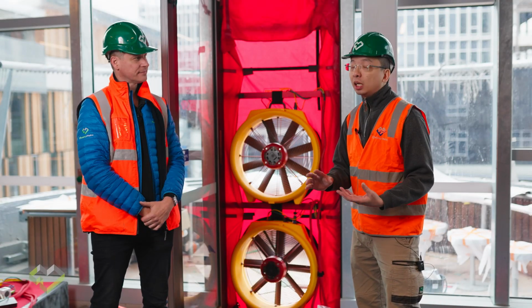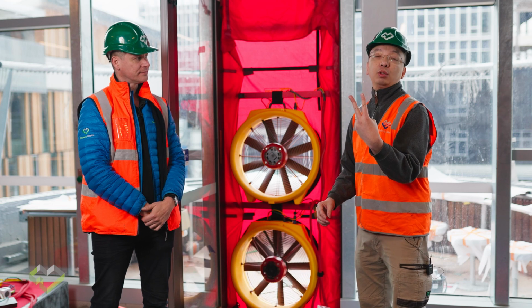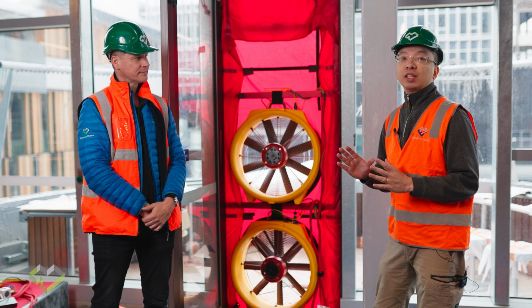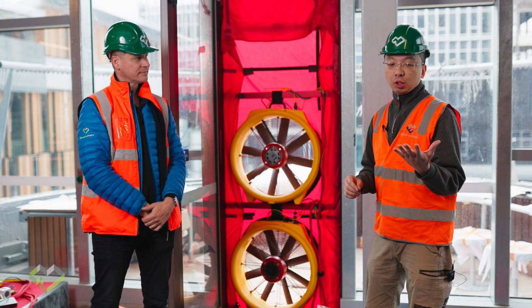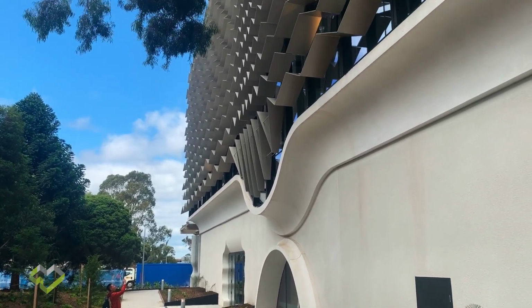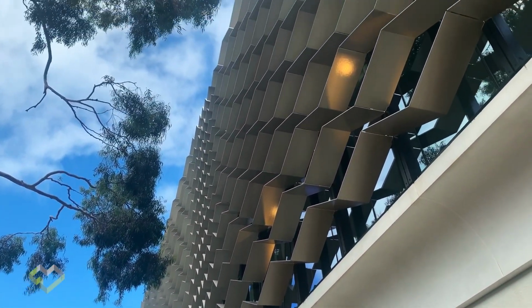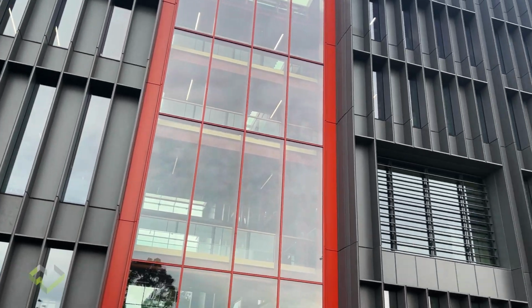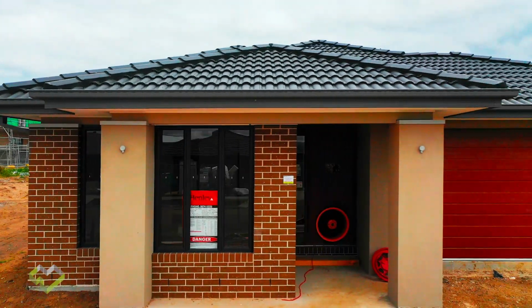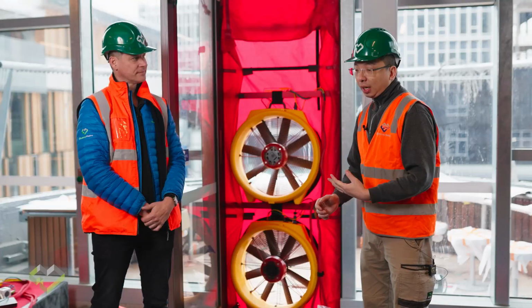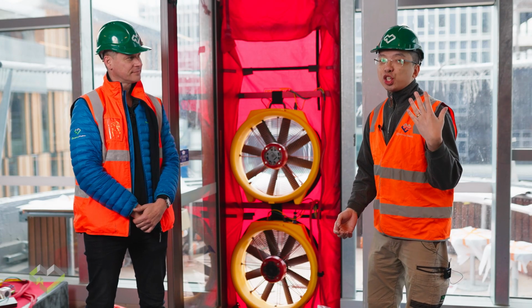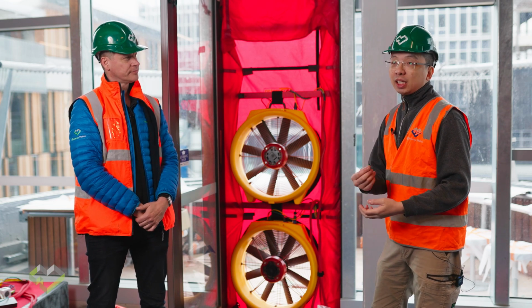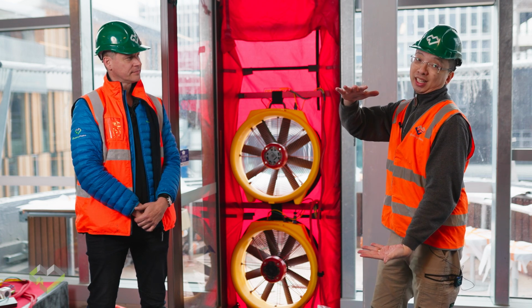That's why typically we have two types of method to present the result. One is what John just said, the permeability rate, which is aimed to compare the build quality between buildings, because it's normalized to the surface area of each building. So it doesn't matter whether you are building a large or small building, the numbers are comparable for each square metre of surface area. On the other hand, the air change per hour uses the volume of air we pump in divided by the volume of the building.